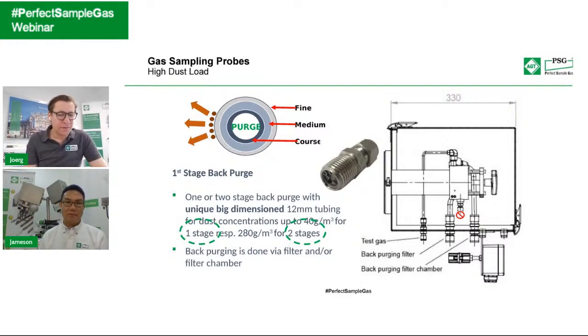But you have to make sure that the pressure is reduced before it goes to the heated sample line. The heated sample line is usually heated up to 180 degrees C. The components used inside, with PTFE, get like chewing gum, so they cannot hold a bigger pressure. And therefore, it's a smart technology.